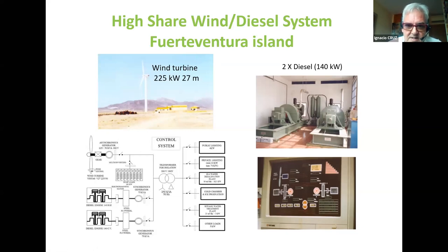This is a wind diesel system. The important thing about this system was that it was a high share wind diesel system. That means the system was able to operate, during periods of high wind, without any diesel consumption—both diesel engines were shut down, and the system was operating, forming the grid, to supply a small village in the south of this island for different loads.